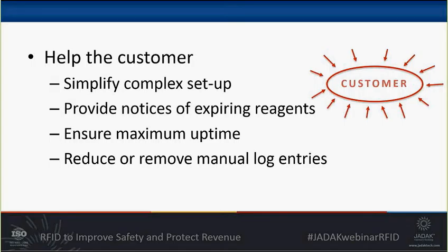There are a lot of different settings they have to put in. It's time consuming. It can take maybe five minutes for a technician to do this for each system and each reagent that we're loading into the system. We use an RFID tag to include data about the reagent being inserted into the system. The machine can then reprogram itself based on which reagent is being used and which test is being run. It can also check whether that reagent is nearing expiration, and if it is, the system can notify the technician that more of the reagent should be ordered, thereby ensuring maximum uptime of the machine and preventing any out-of-stock situations where we have to wait an entire day until we can run a particular test on urine.